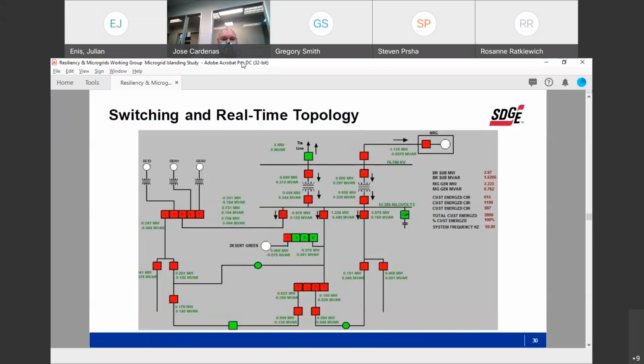So one thing we leverage here is the solar, right? We wait 5 minutes for solar to kick in to increase how much load we can pick up during these island events. With that being said, when we do the next load step, we have to make sure we can pick up that whole load step. As Devon said, it could be 2 to 3 times the steady state value for your inrush. We have to make sure we can maintain the frequency, because say we go 2 to 3 load steps into this process and your frequency goes out of balance, you're going to lose all the solar that you had previously picked up that you were depending on during that operation.